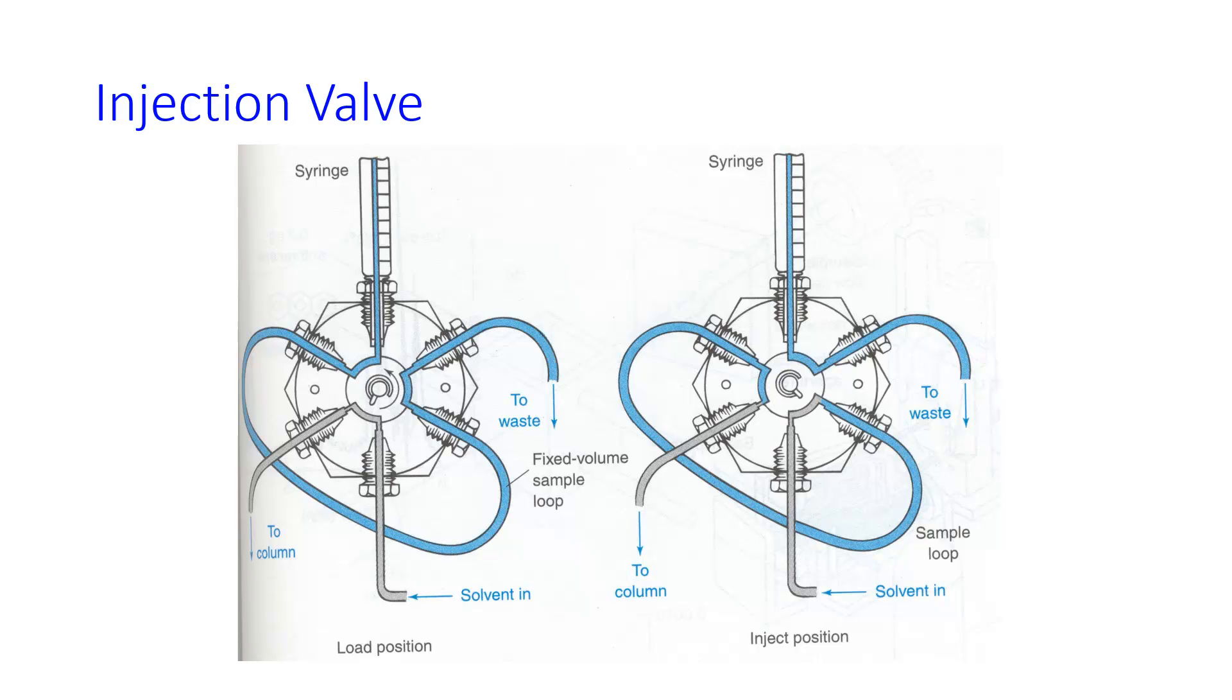So the injection valve is where your sample gets introduced into the instrument. And injection valves have two positions, the loading and the injecting position. In the loading position, the syringe is connected to an injection loop, or a sample loop, that has some volume. They have all different volumes. And when you inject, you fill up the sample loop, and then put a little extra in until you see drips coming out of the drain where it says to waste. That's how you know your sample loop is full.